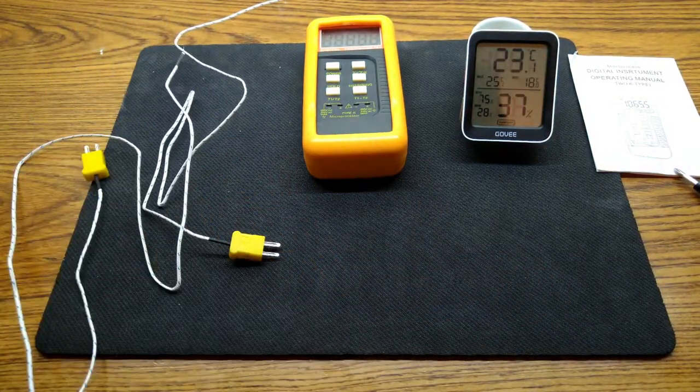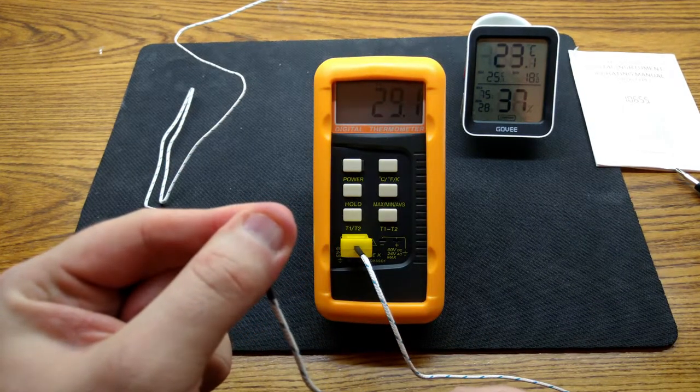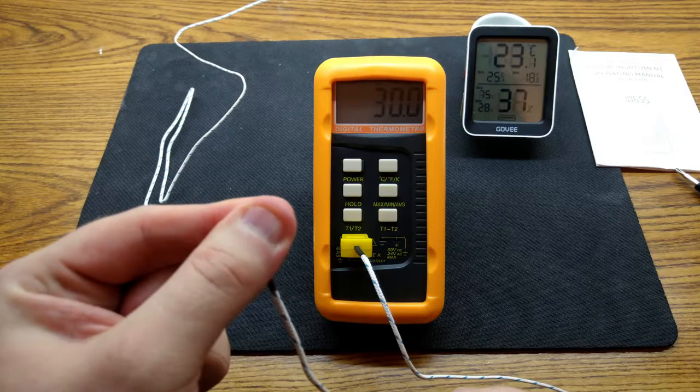The thermal response time of the probes is around 10 seconds to reach a steady-state value. So when applying this to a heated load, it takes around 10 seconds for the temperature to become stable.